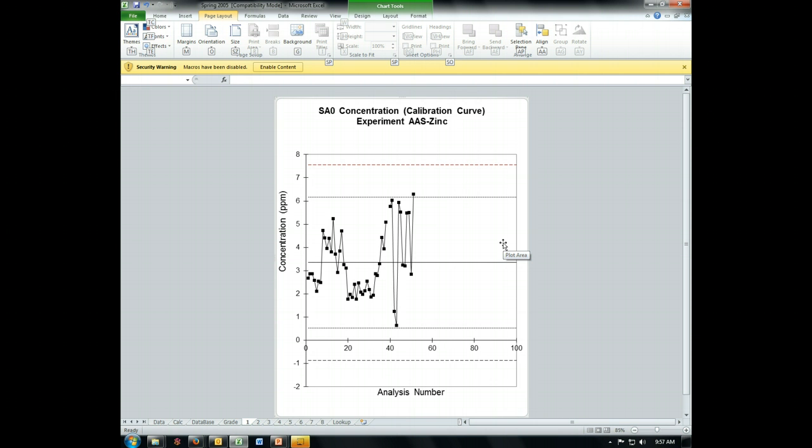The fourth one, also in that box, 5.1 on page 99, they say if 6 consecutive measurements are all increasing or all decreasing, that's a reason to shut down. We go up, up, but down. So if this one had been just a touch higher, we would have had 1, 2, 3, 4, 5, 6. If this had been high enough that this was still rising, that would have been a reason to shut down. You can see here that we don't have a consecutive pattern. There's enough jitter back and forth that that's still a sign that things are behaving randomly.